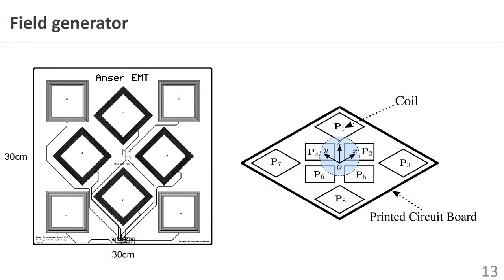Anser EMT features a printed circuit board field generator comprising eight discrete coils. The location and dimensions of each coil are precisely known relative to the center of the circuit board. A frequency domain multiplexing approach is used where each coil transmits its own distinct frequency in the kHz range.